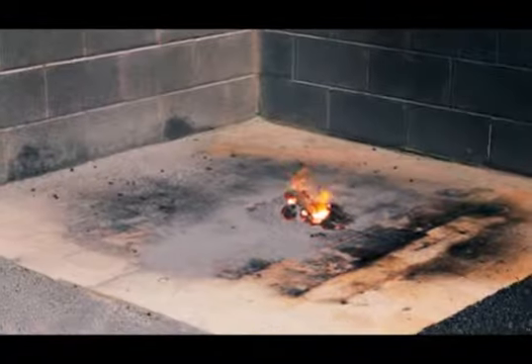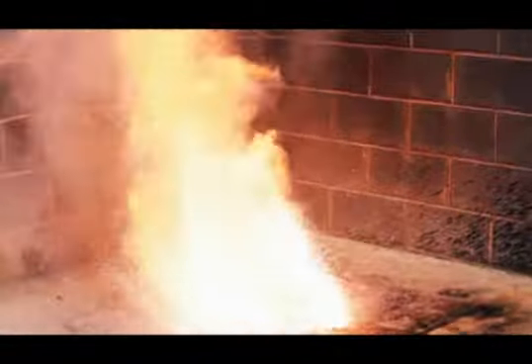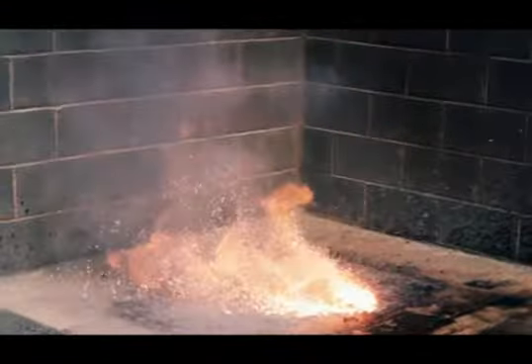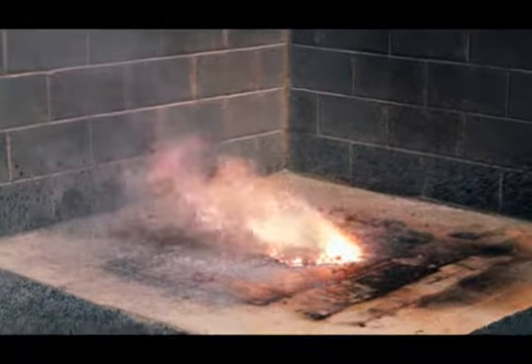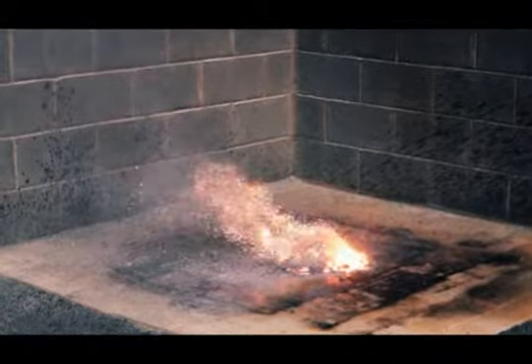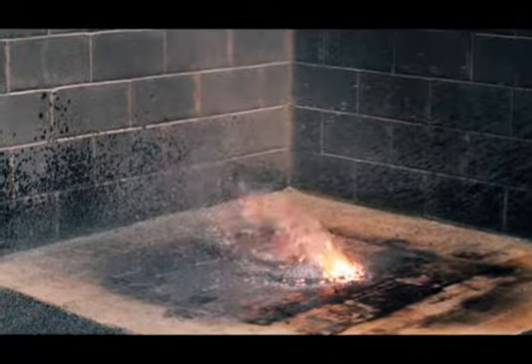Water must never be used to fight an aluminum powder or paste fire, since the water will react with hot aluminum powder to form highly explosive hydrogen gas. The force of the water hose stream may also suspend the aluminum powder and form a potentially explosive dust cloud.